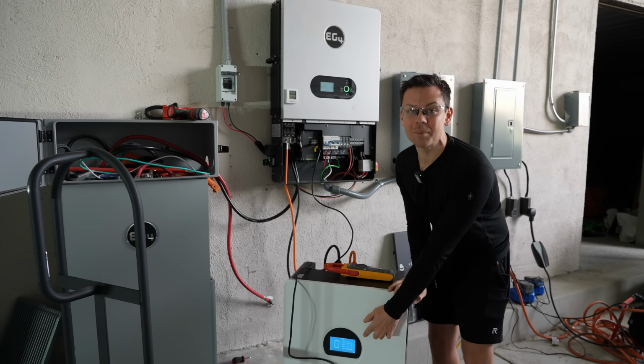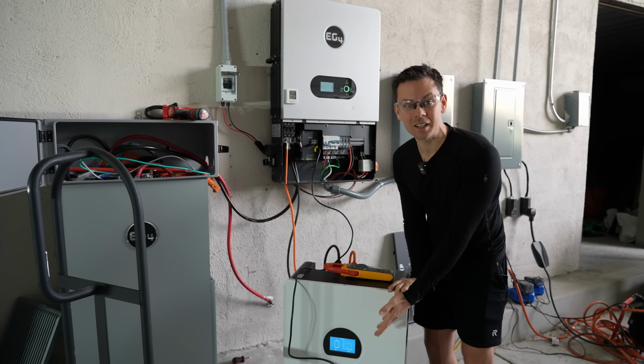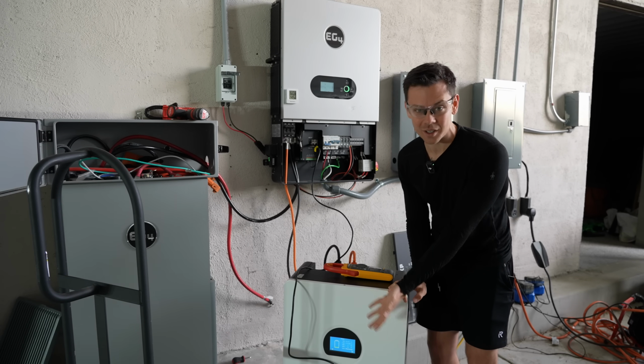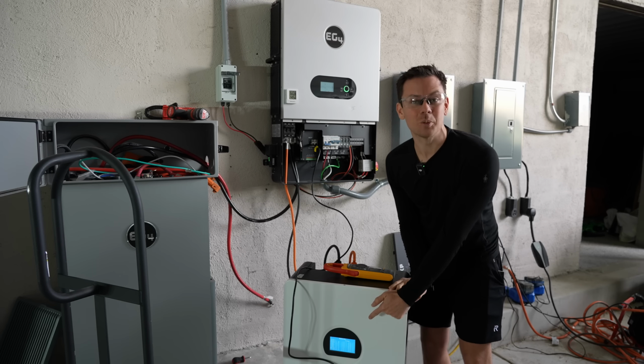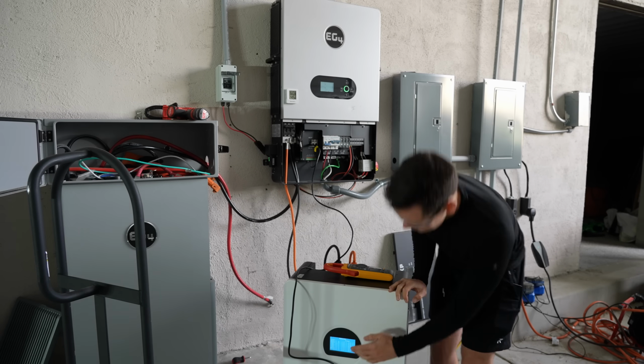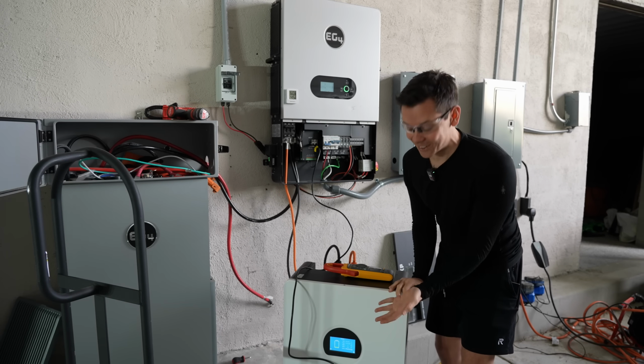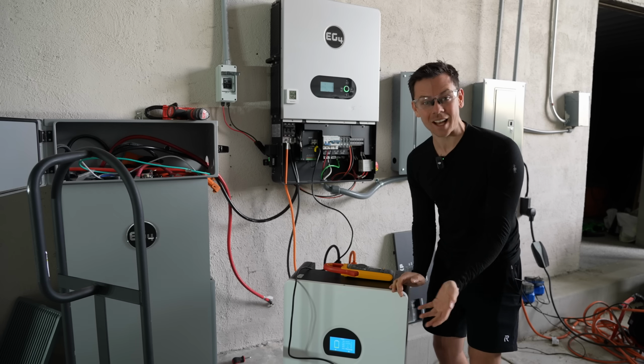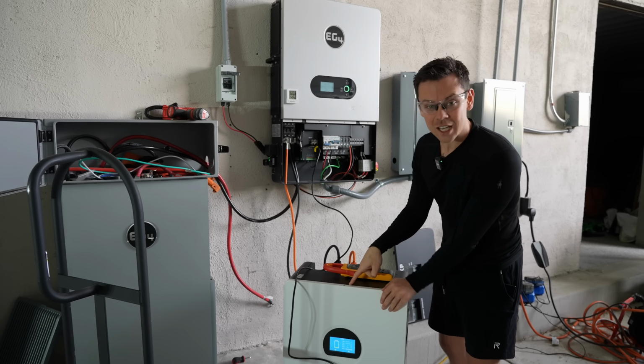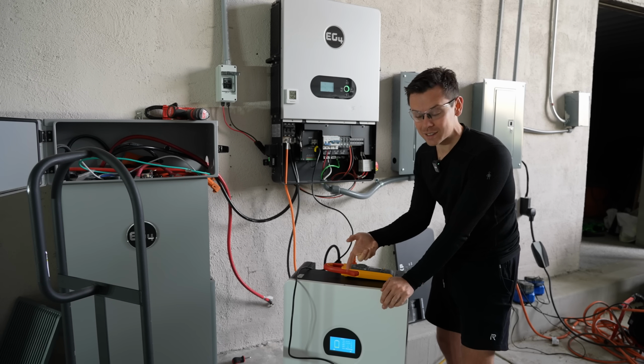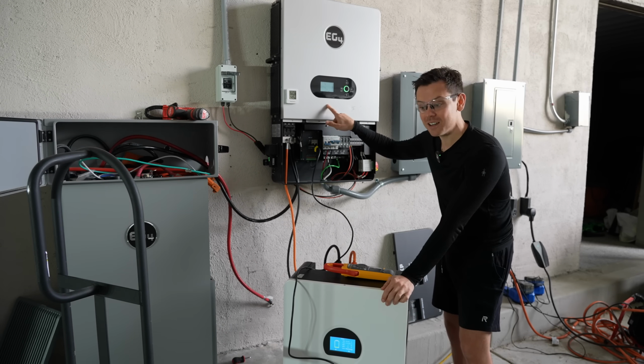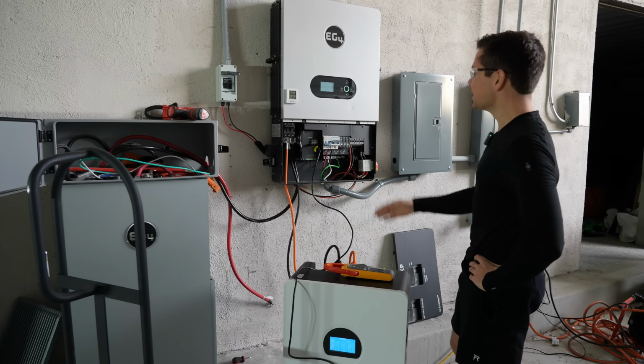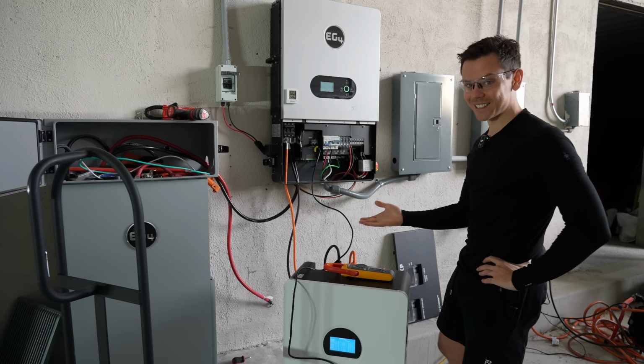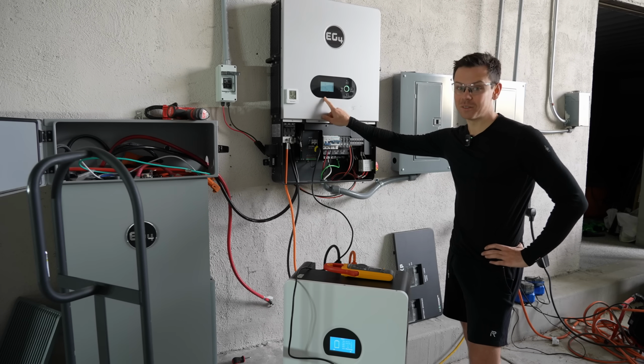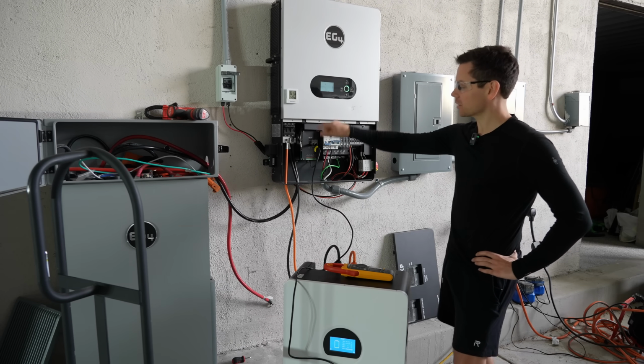I don't think we can get much lower. I think it's anticipating 314 amp hours, but we're not getting that. So the battery says 28 amp hours are remaining, but we're at 49 volts, so it's not gonna pull it off. I think that's what was happening. The communication system thought it had more capacity, but the inverter was saying, hey, no, it has low voltage. So it was the battery's fault.